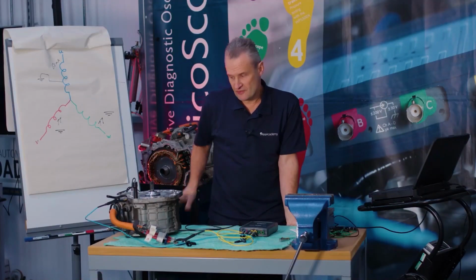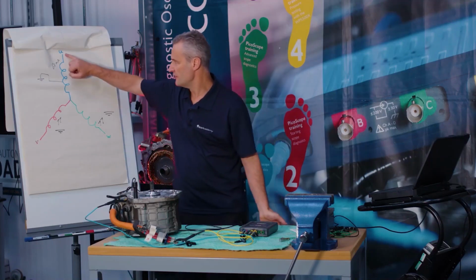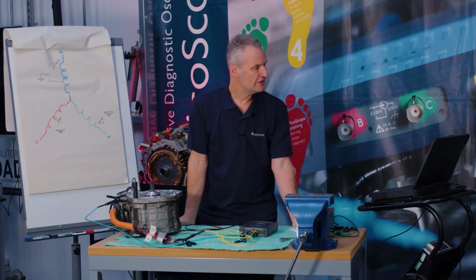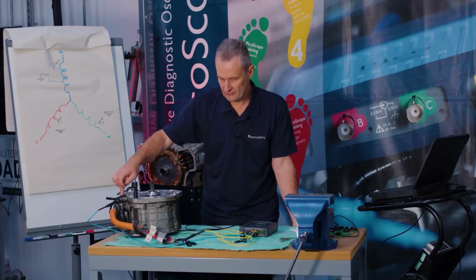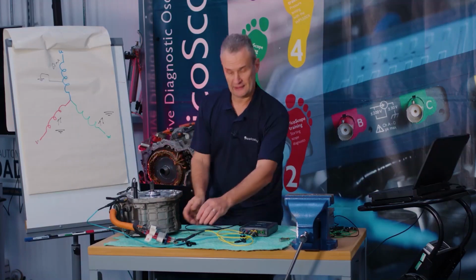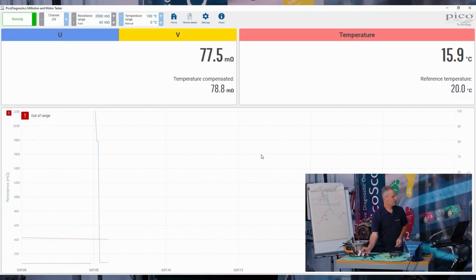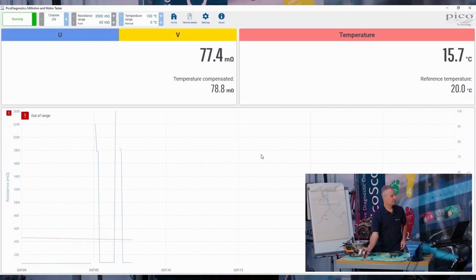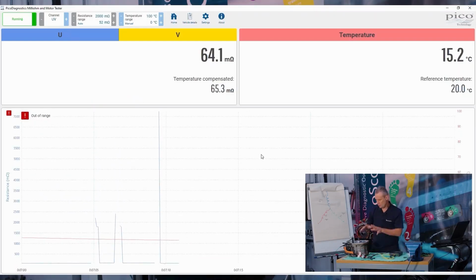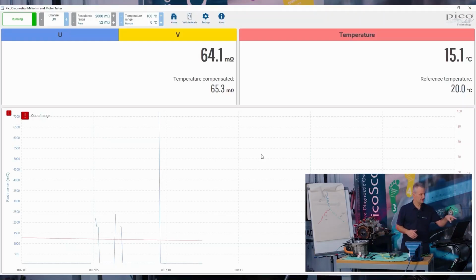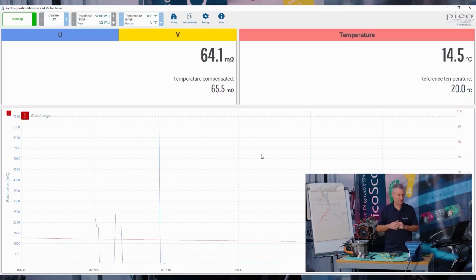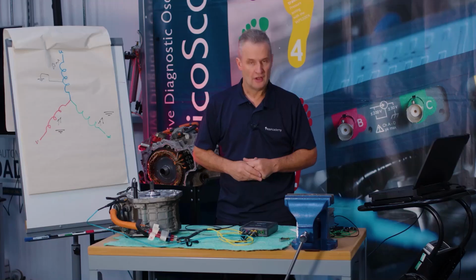Okay, just to recap before we dismantle this motor, we're set up to measure the phase resistance U to ground. You see there we are at 64 milliohm on U to ground. There's our ground clip, there's our U clip. Just to quickly run through again as a refresher, what had we got on the V phase? 77. And the same again, 77 on the W phase as well. All right, we'll leave that logging whilst we take components off. Remember, we are temperature compensated, so the results at the top are the current measurements and the results underneath are temperature compensated. At 14 degrees, we'll actually be adding a resistance value, because we know that as temperature increases, with a positive temperature coefficient, the resistance of the copper will increase too. All right, let's get going.